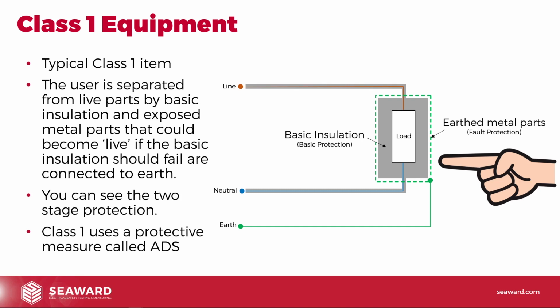They'll do an earth continuity test on the guard around the blades, and they'll say there's no earth there, that's not earthed, it's faulty, chuck it in the bin. Whereas actually if you test on the motor that's meant to be earthed, perfect, you've got a perfect earth connection, so the actual shock protection, the ADS, is there, it's all working. We've got basic insulation, we've got our earthed metal parts, and we've just got unearthed metalwork in part of that process. And if we test unearthed metalwork and it fails an earth continuity test, don't be surprised.